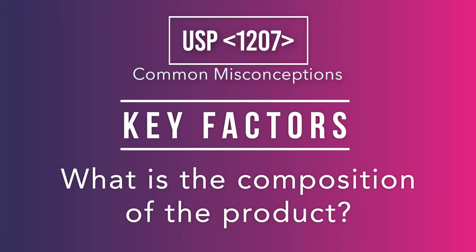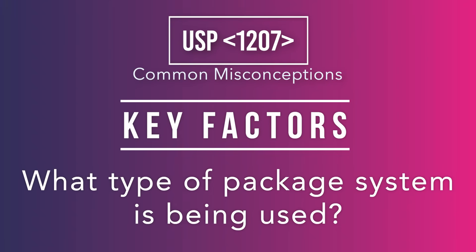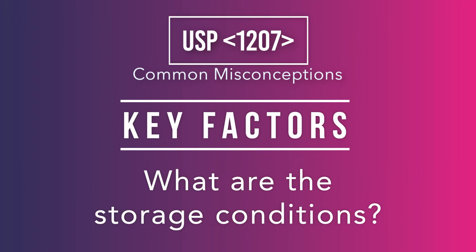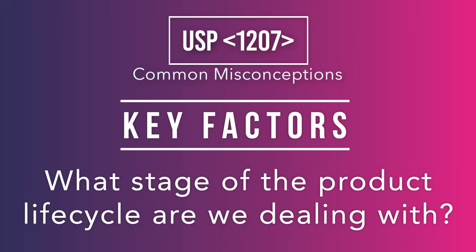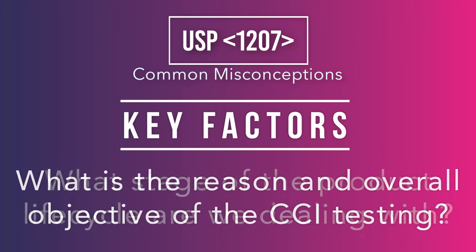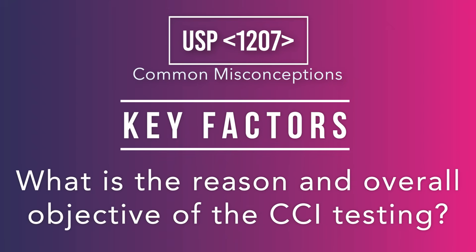What is the composition of the product? What type of package system is being used? What are the storage conditions? What stage of the product life cycle are we dealing with? What is the reason and overall objective for the CCI testing? Understanding these critical issues will help to define the optimal method for that specific system.